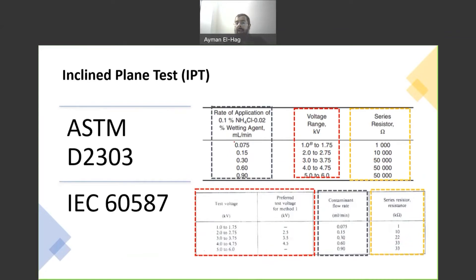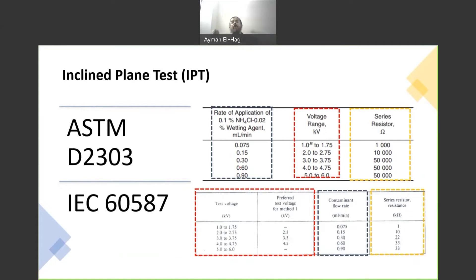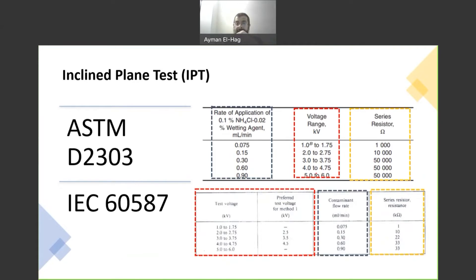This is the flow rate — how many ml per minute we have to supply using the peristaltic pump — and they are exactly the same in both standards. So you can see there is a combination between the voltage, the series resistance, and the flow rate, and you have to make sure these three items match each other. For example, if testing at 4.5 kV, the flow rate has to be 0.6 ml per minute. The limiting resistor, if using the ASTM standard, has to be 50 kΩ, and using the IEC standard, it has to be 33 kΩ. This is the most important information you need to know about the standard.